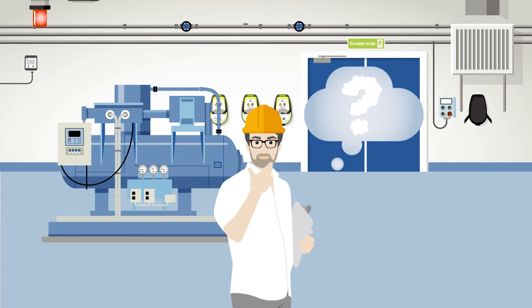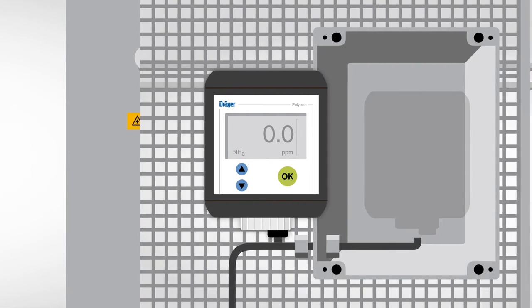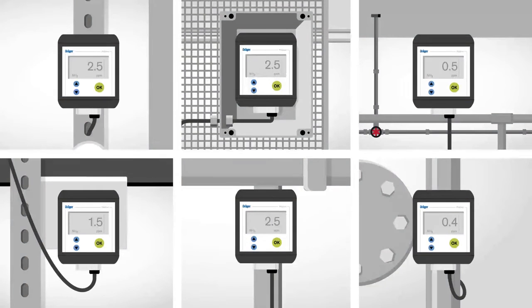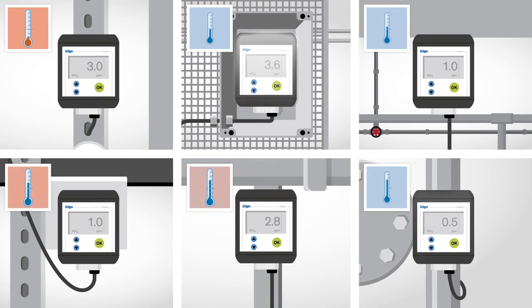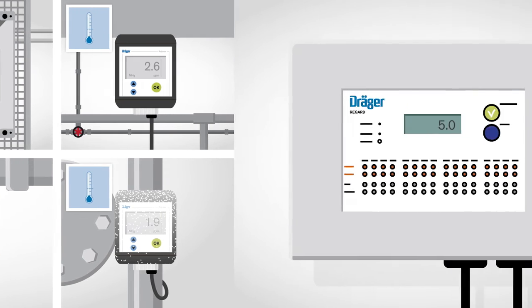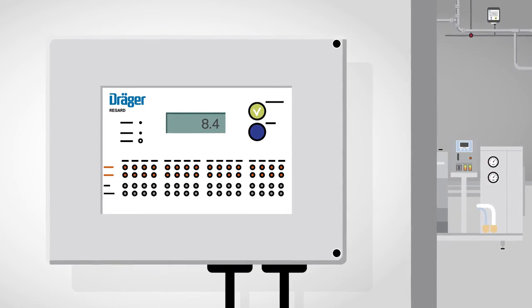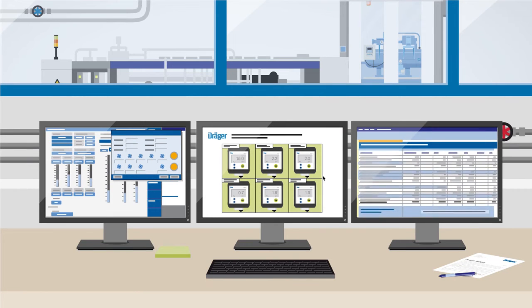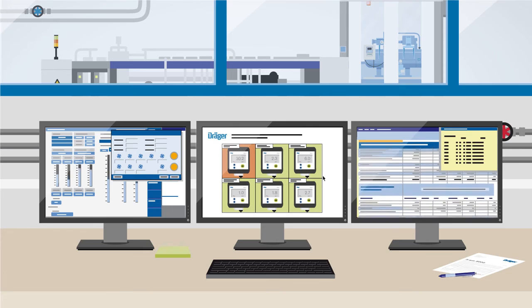The safety engineer is responsible for the measures which ensure a safe usage of ammonia in the plant. Fundamental to the safety of the plant is a stationary gas detection system. For early detection of gas leaks, a number of transmitters are fitted in the compressor room, the valve stations, and also perhaps the cooling chamber. The temperatures vary significantly in these different places — whether warm, fluctuating, or cold, the sensors must master these rough conditions and precisely measure the NH3 concentration and respond immediately at all temperatures. The measured data is processed through a control system that interprets and translates the electronic signatures of the transmitters, then outputted via a panel in the control room. The installed sensors report gas leaks according to the defined alarm levels.